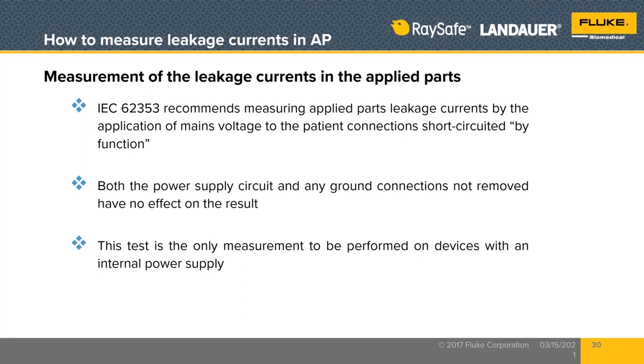Now you may remember under 60601-1, we use 110% of mains. But under IEC 62353, we just use the mains voltage on these patient connections. If they are an F type, meaning BF or CF applied parts, we just need to group those all together by type. So that would be all ECG leads and the invasive blood pressure leads shorted together and tested with 100% of mains power to test the isolation barrier that it protects the patient. That's what that test is for. That is the isolation test, okay?